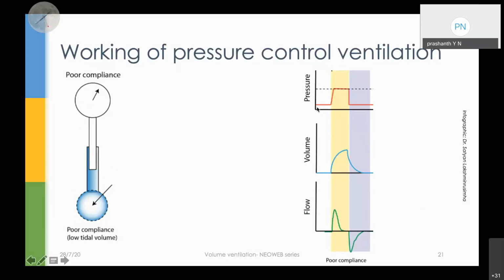Here you have a breath which is kicking off, and we have a set pressure. We have set the ventilator to give this much pressure through the inspiratory time. The yellow bar represents the inspiratory time. So it gives so much pressure for so much time, and then it goes down, and then it cycles. Depending on this pressure, you have the volume which is rising, and after the pressure comes down, your volume also goes down. So do your flows. All right. Assume that you guys are clear.